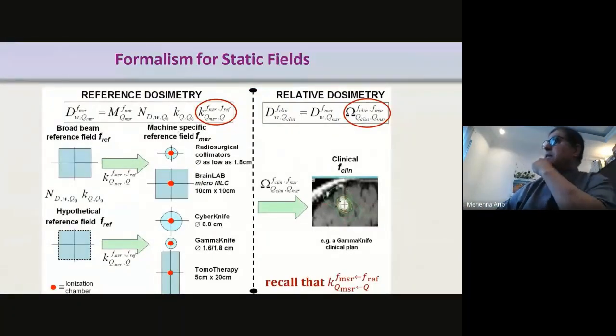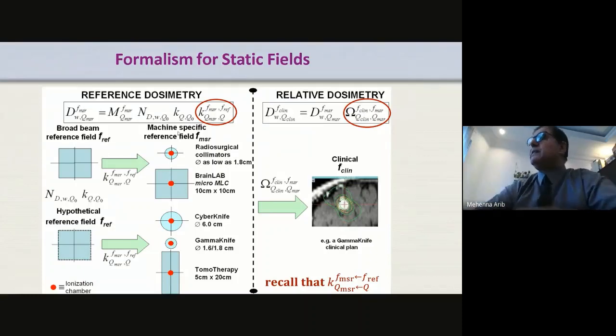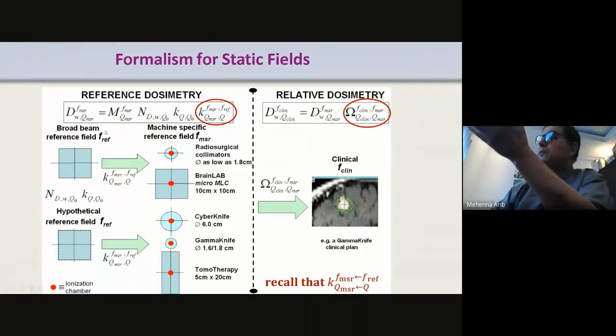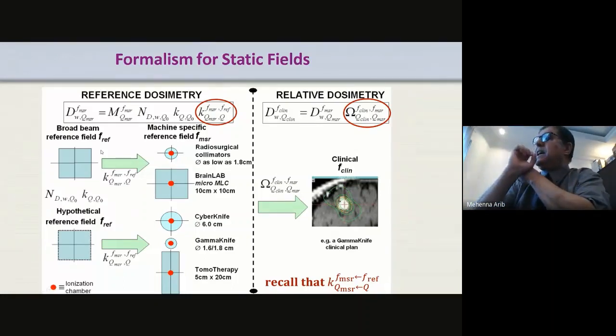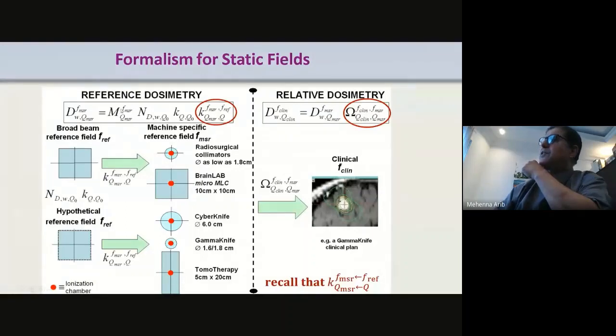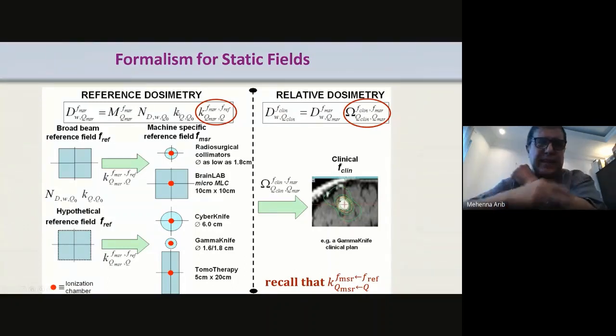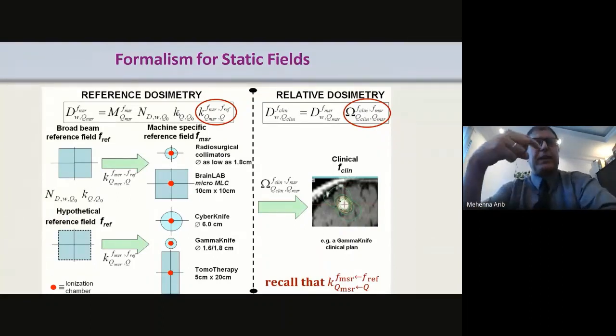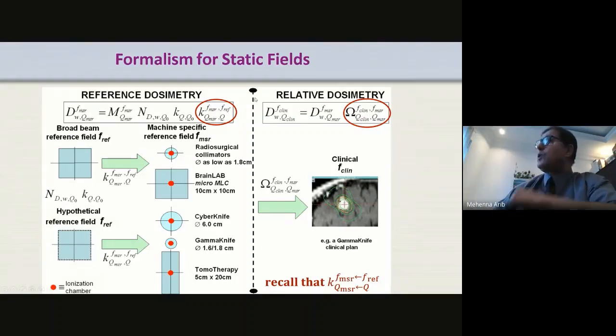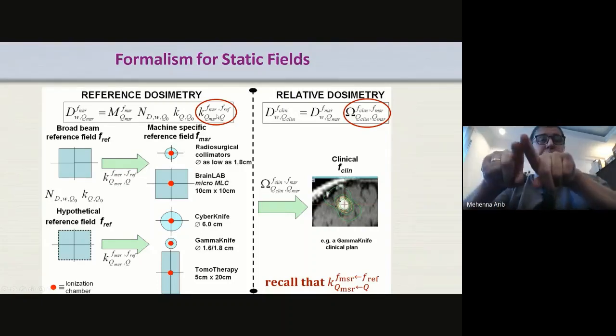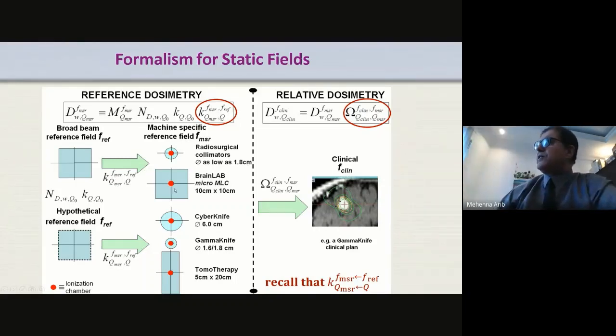And so, in terms of formalism for static field size, we have the reference dosimetry, which you can see here, which gives the absorbed dose for this machine-specific reference field. It starts from the reading of the chamber and the calibration factor in cobalt, and you have here the calibration conversion factor, which is similar to TRS-398, which gives a calibration coefficient for the high energy beam starting from cobalt-60. But now you have an additional factor which converts this calibration coefficient to the small field or to the machine-specific reference field. For the conventional linear accelerators, we have 10 by 10.